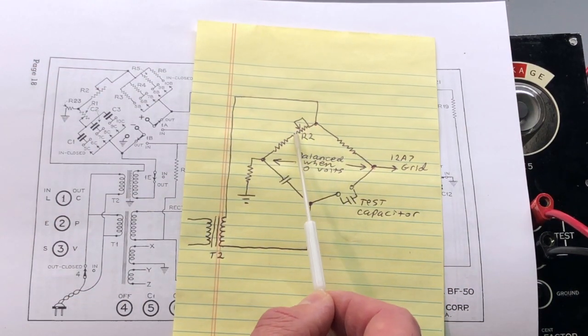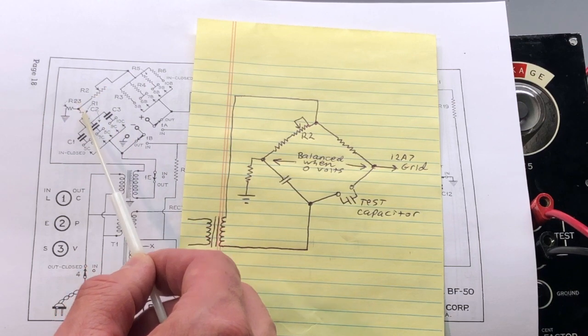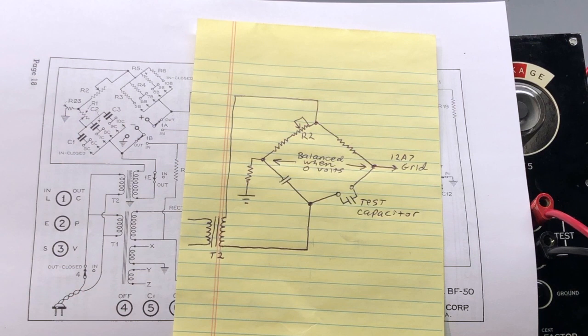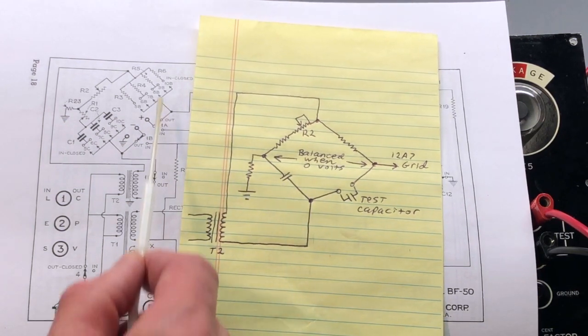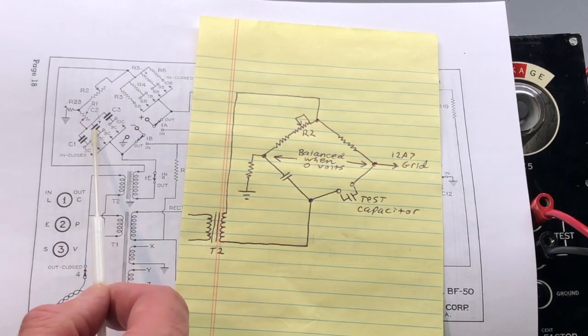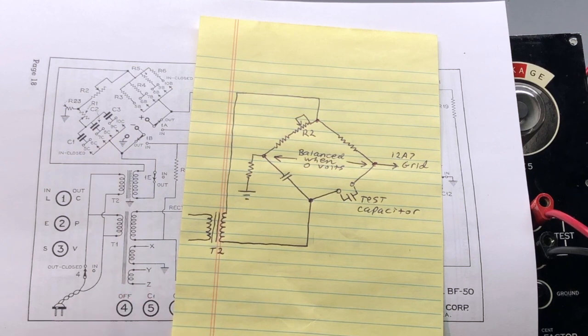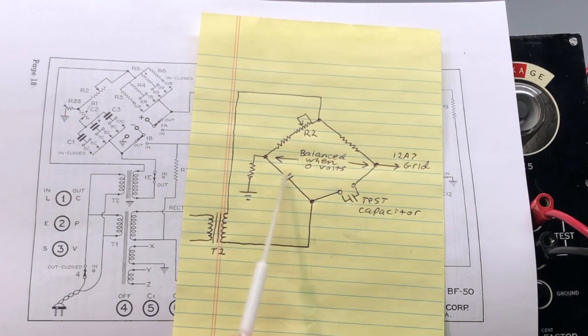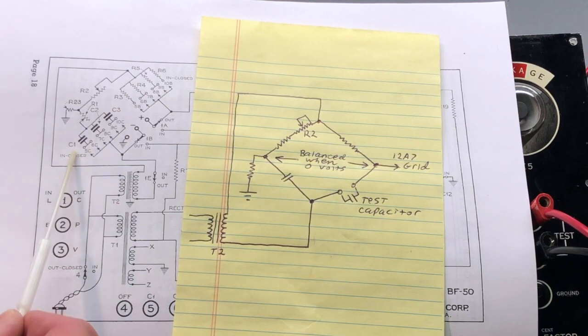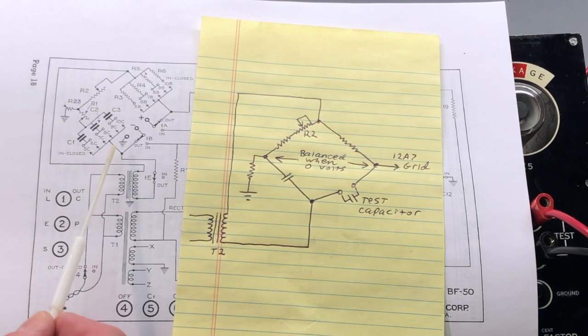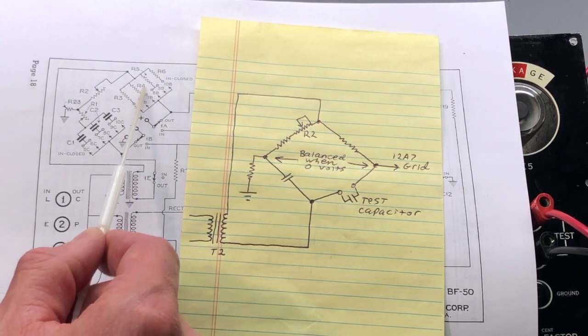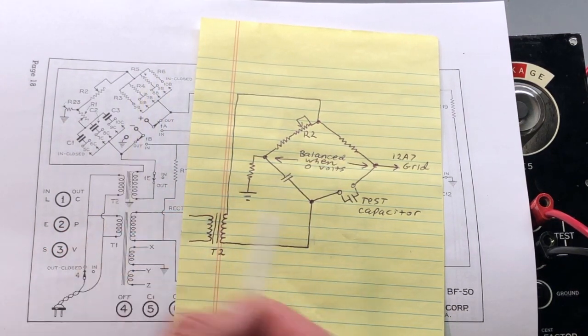R2 is that main dial adjustment that you turn. So that's a variable resistance. And you can see that over here. And then another resistance, R1, which is the power factor control or adjustment. So I've just drawn that as a fixed resistor over here for now. And this resistance and this capacitance right here, on the schematic we have this resistance and the capacitors here. Those are selected by the test switches that are selected during the test. And for simplicity, I've drawn it just as one capacitor because that's all that is selected at any one time. So they have 3 capacitors, but depending on the range of capacitance that you're checking, only one is selected. Same with the resistors. We have 4 resistors shown here, but only one at a time would be selected. So again, we have 1 resistor.